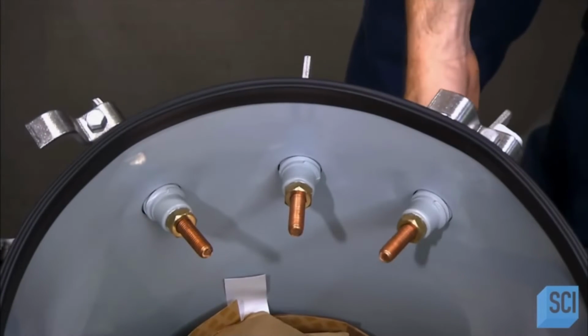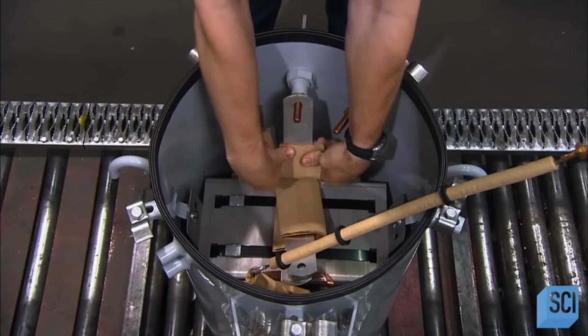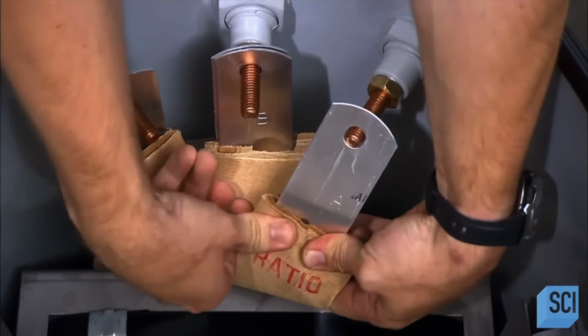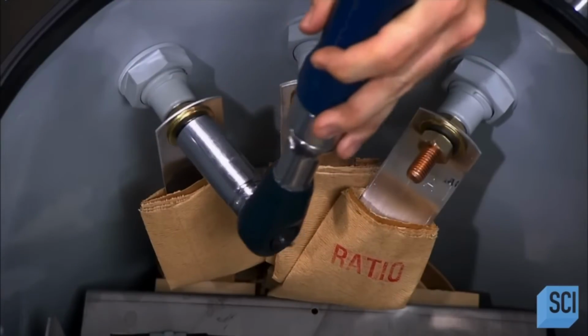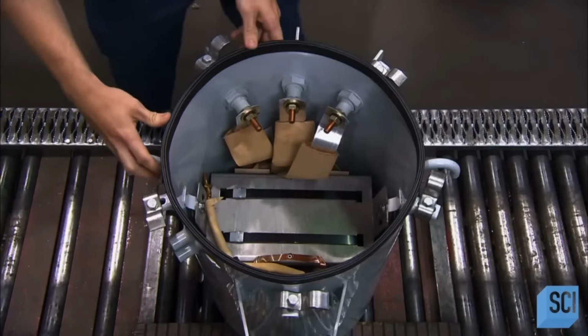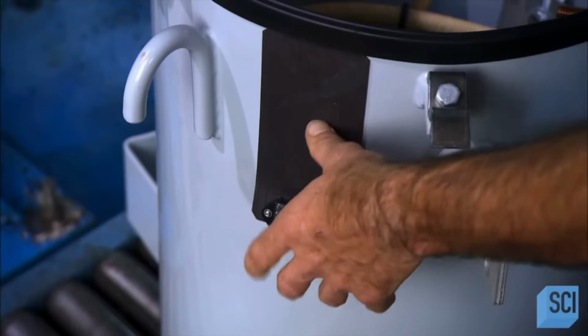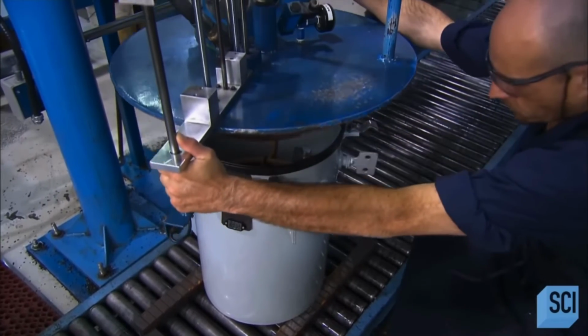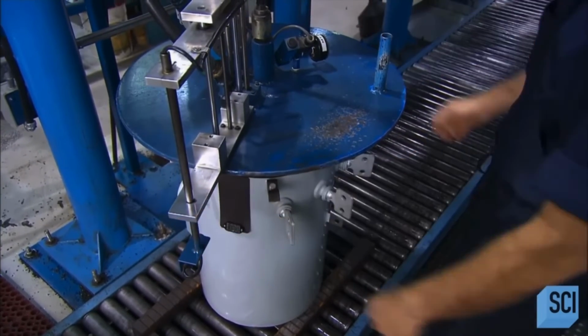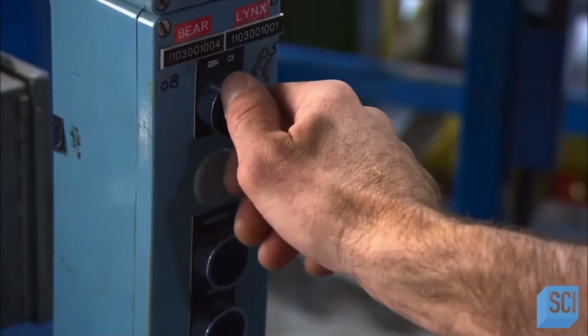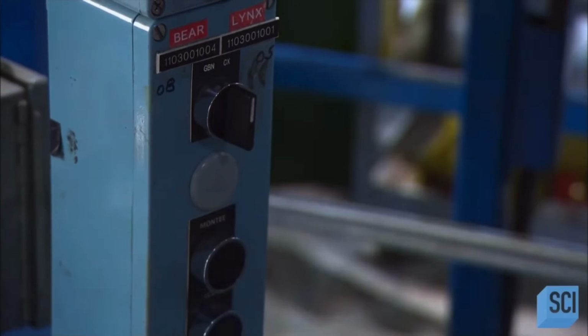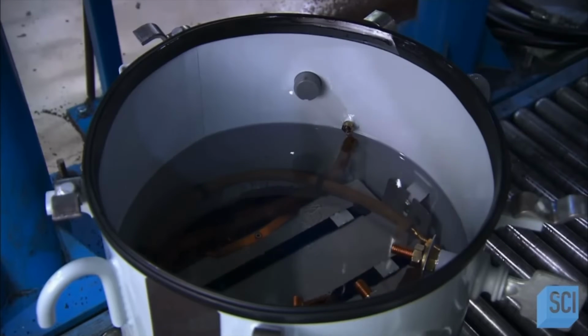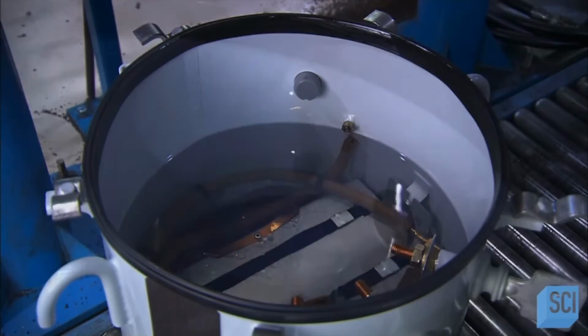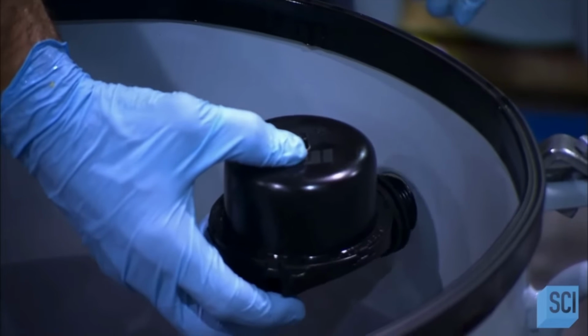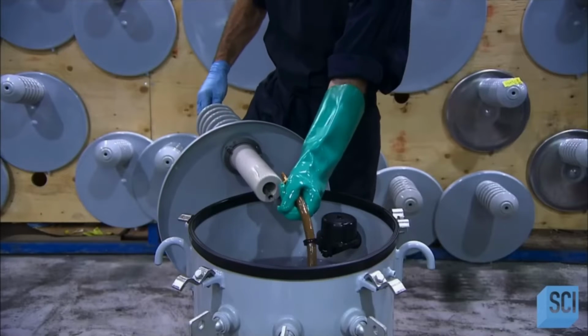Then 3 thermoplastic bushings are inserted. Workers connect the low voltage lead to the thermoplastic bushings, then bolt the bushings to the tank. They adhere an oil filling guide to the side of the tank, then position an automated filling machine. A machine fills the tank with mineral oil, drawing a vacuum to make sure the oil disperses throughout the coil and core. The oil is used for its thermal and insulating properties. An internal fault detector will alert maintenance crews if there's a short circuit.